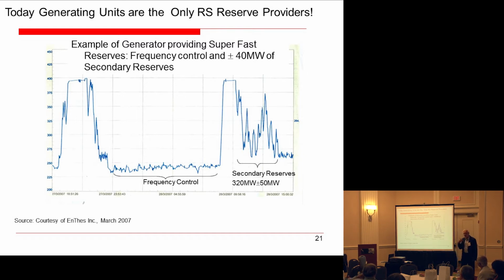So you can provide less frequency control than secondary reserves, where the ramp rate is less demanding. If you promise 5 or 10 megawatts of regulation reserve, you should be able, within 2.5 minutes for fast or a longer period for regular, to jack up or decrease your generation by that amount. So then you can provide much more: with the same ramp rate over 30 seconds instead of 5 minutes, you can provide one-tenth the frequency control compared to regulation.